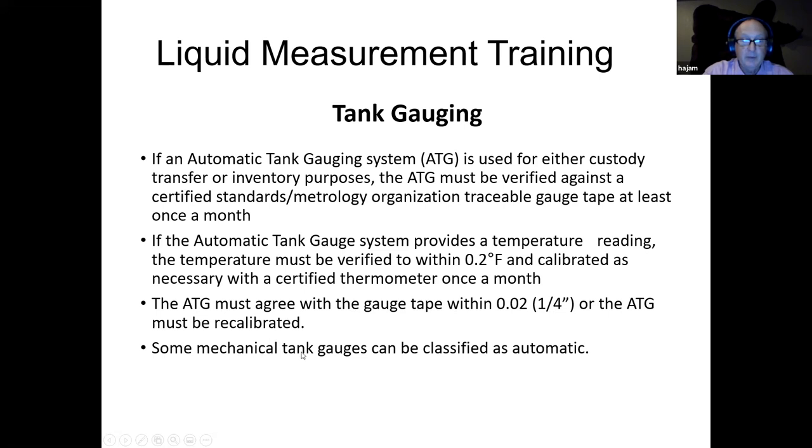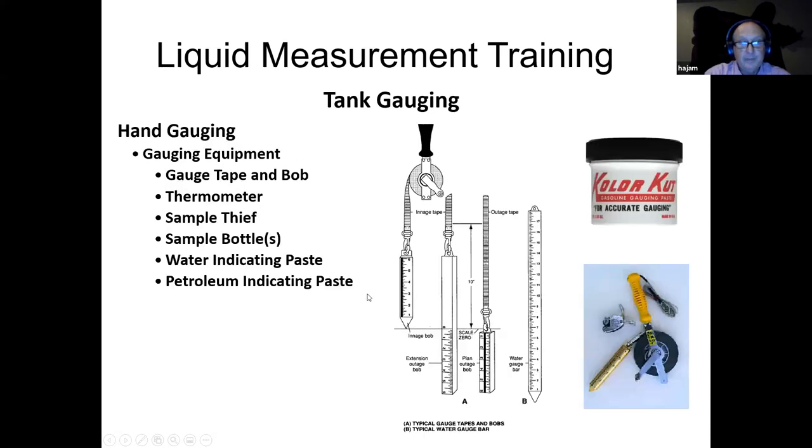And again, I want to re-stress that I have been in cases where I've been told many times it's an automatic tank gauge, only to get out there and find out it's really a mechanical sideline gauge. And we have been taking deliveries from that automatic tank gauge, or supposed automatic tank gauge, for quite some time. So you want to be aware that mechanical tank gauges are not considered automatic tank gauges.